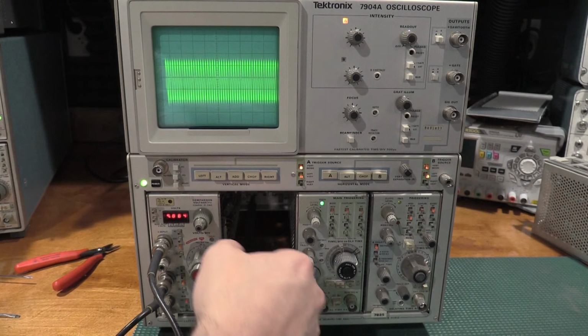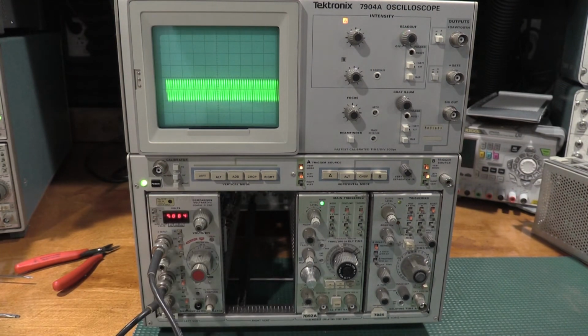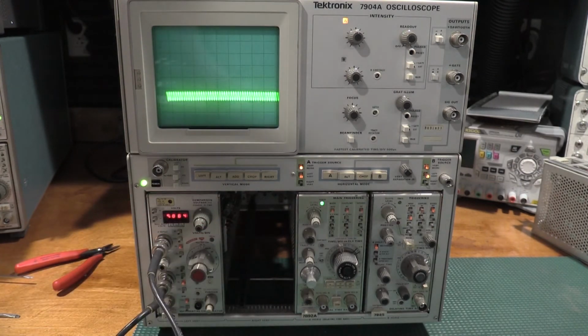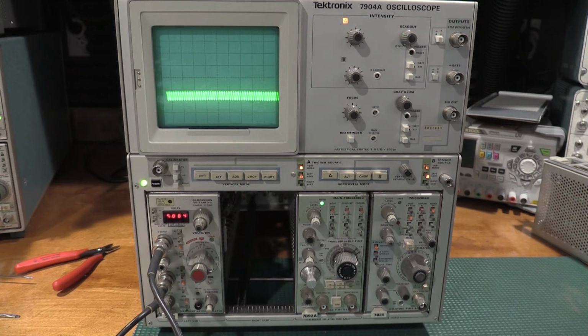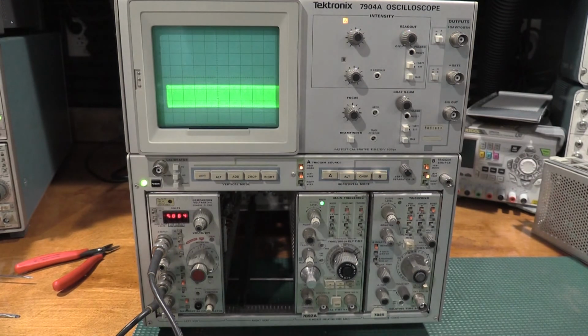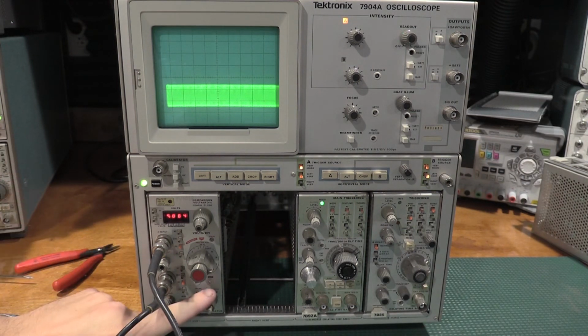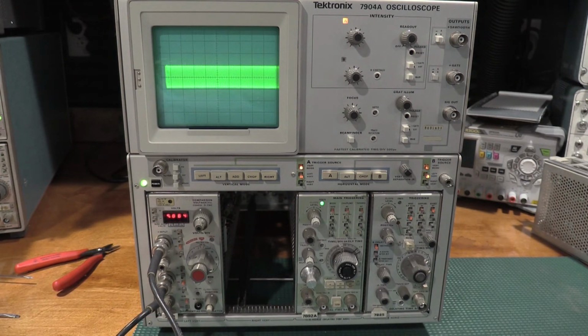And now we need to kick this to 2. And we make it just barely. So let's check 20. Amplitude 2 divisions or less, so we make it just barely. So we got 500 to 1. 20 megahertz at 0.5. So crank this up to 20. And I should have 4 divisions or less. Oh yeah, we do. Very much so.